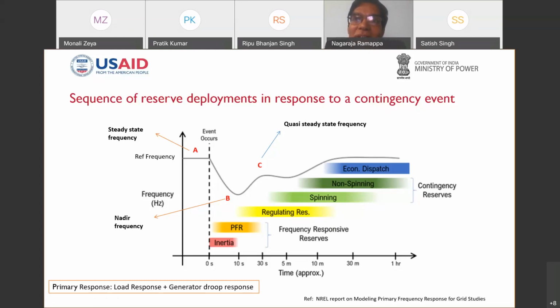In fact, the H, which is defined as stored kinetic energy divided by the rating of the machine, normally is in the range of 2.5 to 3 seconds. Therefore, if you take the entire southern grid of about 40,000 megawatt, as an equivalent machine of 40,000 megawatt, it has an inertia constant of say 3 seconds on its own rating. It tells us that if the electrical power becomes zero, with full shaft power there, or the mechanical power or the generation is lost and the electrical power is fully available, it takes 2H seconds for the speed to become zero from 50 hertz. That is why H is called the starting time constant. With the inertia constant not being there, this response we need to curtail. Therefore, that is very important.